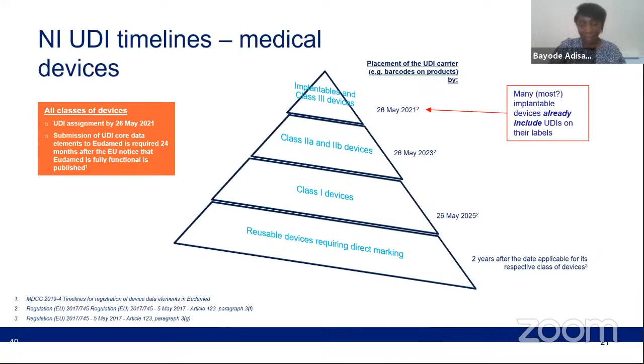So we're now in a situation, as we've reached the 26th of May 2021 deadline, where implantable devices and Class 3 devices should all have UDI assigned to them, and the UDI should also appear on the barcodes of the device labels. So all of these devices that are entering the EU market or NI market should be labeled with UDIs. In 2 years' time, we'll also be in that same situation with Class 2A and 2B devices. In terms of IVDs, UDI assignment for all classes of IVDs is required by 26th May 2022. In terms of the placement of UDIs on the device labels, it will be a requirement for Class D IVDs by the 26th of May 2023. So these are things like HIV tests and fall under this category.